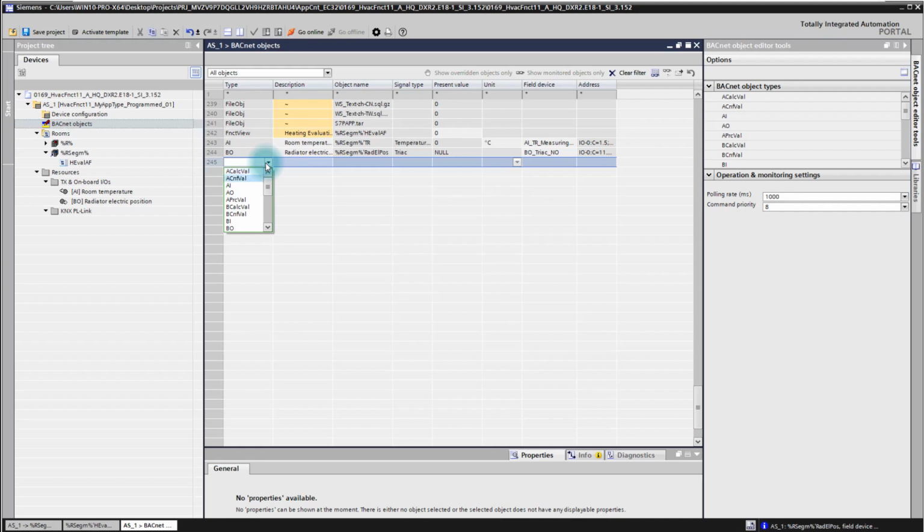The configuration value, that's the one which we use for the set point. So that's the data points where you then can write and change in your system. So that's the one we want to use then later on. But let's finalize the group of our value objects. The last one is the process value, and the process value gives you the opportunity in your CFC code to create an object which can be then also overridden by the system. So that's the three main objects we are using for creating CFC code.